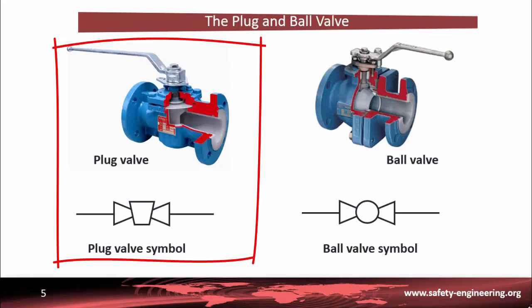A plug valve is a quarter-turn rotational motion valve that uses a tapered or cylindrical plug to start or stop flow. The name comes from the shape of the disk, which looks like a plug. In the open position, the plug passage is aligned with the inlet and outlet ports of the valve body. If the plug is rotated 90 degrees from the open position, the solid part of the plug blocks the port and stops flow.